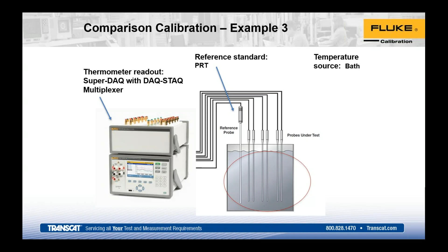And with the dry wells, fit is key. If you have a 1/8" probe, you don't want to put it into a 1/4" hole. You want to match it as best you can. Typically, for a 1/4" probe, the hole that you're inserting into, which would be considered the proper placement, is usually drilled about plus 0.015 bigger. So it's a tight fit that allows just enough for really good thermal conductivity, but not so tight that as things expand, it's going to get stuck. There's that happy medium where it still has to fit as we increase in temperature and things swell a little bit, but we don't want it to get stuck. And ideally, if you're placing on that picture on the right, you want to immerse your sensors at the same level, aligning your reference sensor and the device under test sensor.